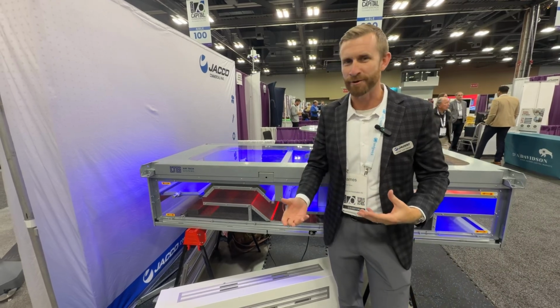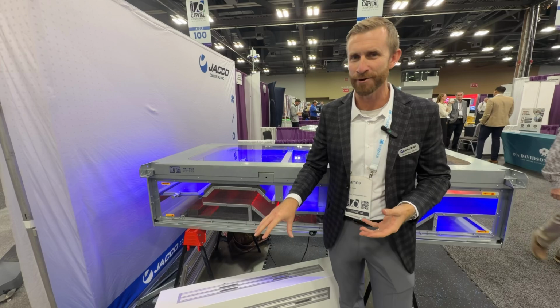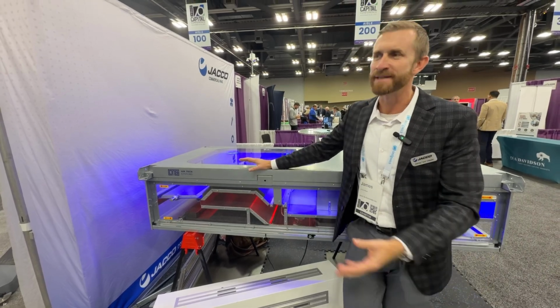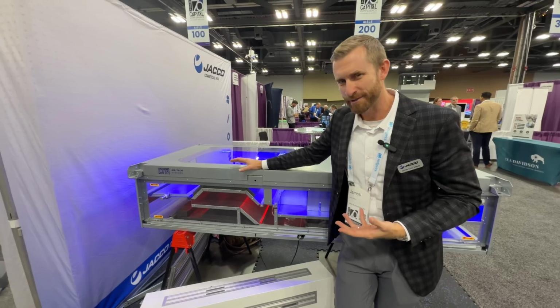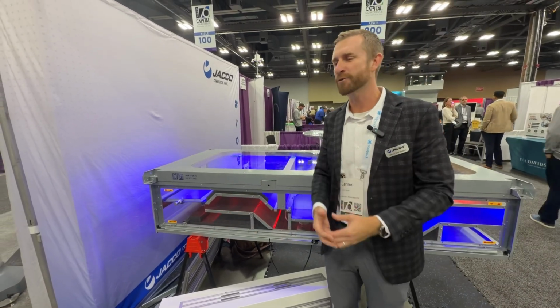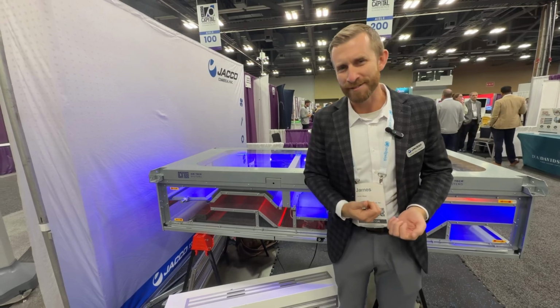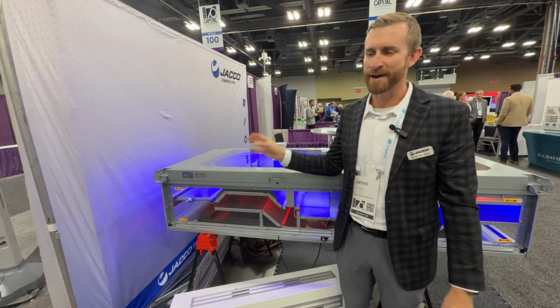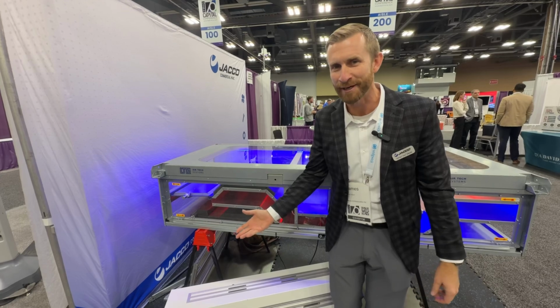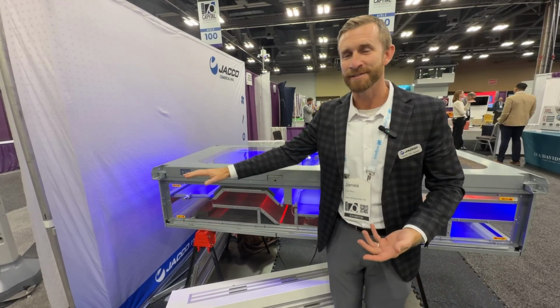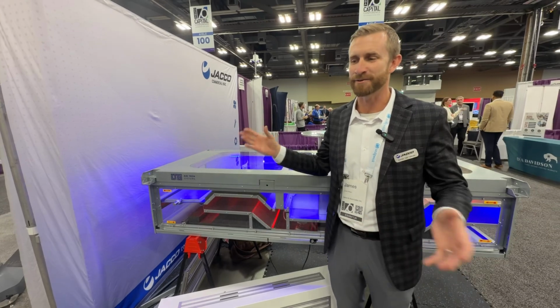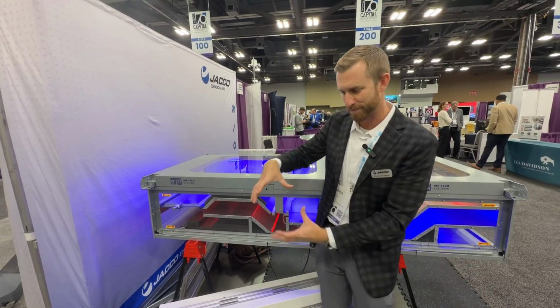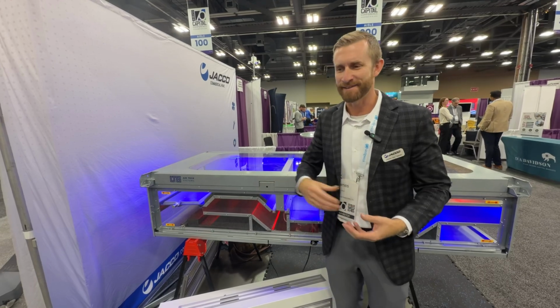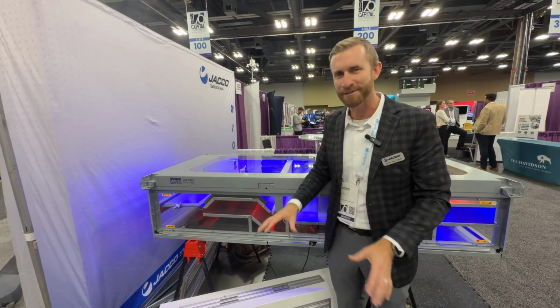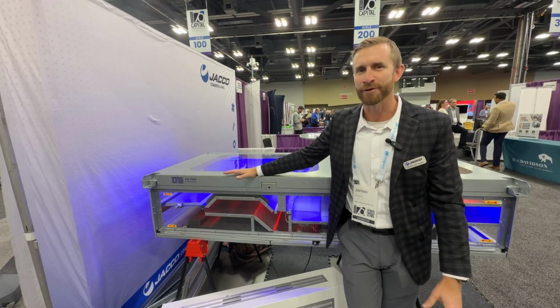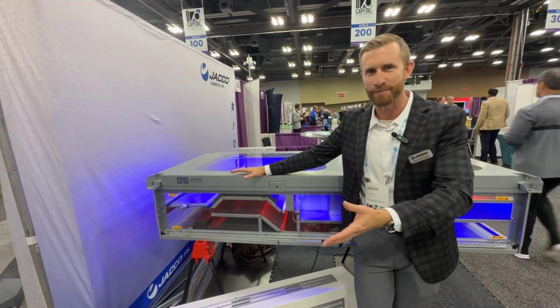And we didn't choose that arbitrarily. We've done a lot of research to find out what's the best condition to learn in. What we have in an old classroom is a unit ventilator and operable windows. So to get that outside air in there, you're asking a teacher to open the window. And if it's 0 degrees outside, what teacher wants to open that window, and how many kids sitting next to that window are going to be comfortable learning with 0 degree air coming into that space? Now, 360 CFM is not like a small fan about this big, like a little box fan. That would be like blowing on a kid at 0 degrees. We don't want to do that. So you want to bring in fresh air for a good learning environment, but you don't want to splash kids with air or make them cold.